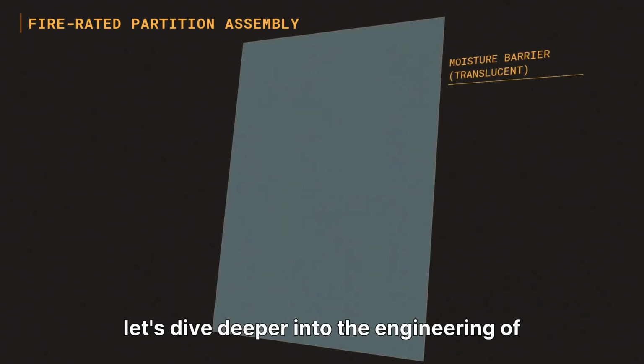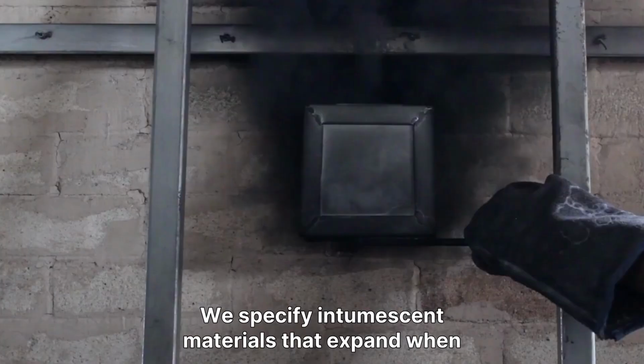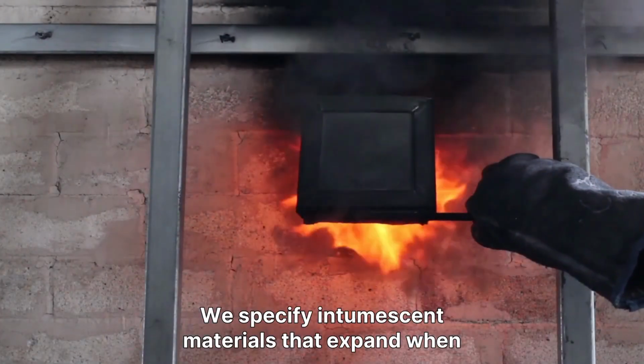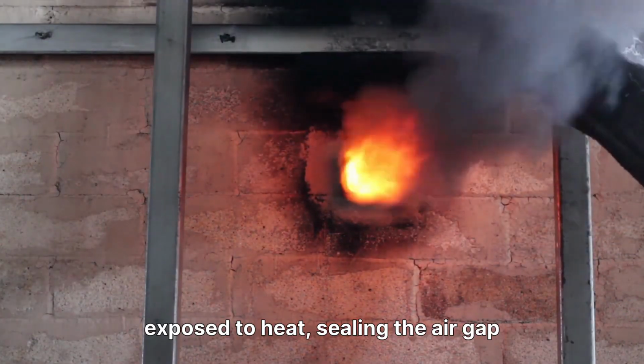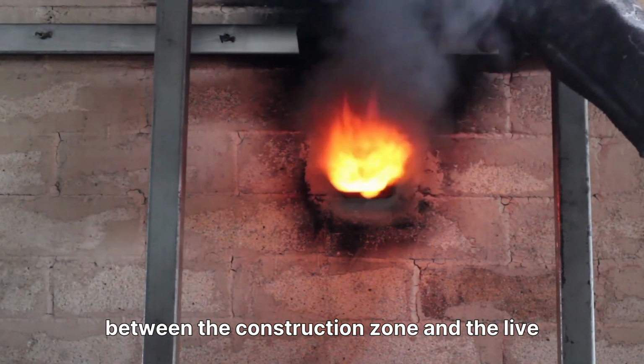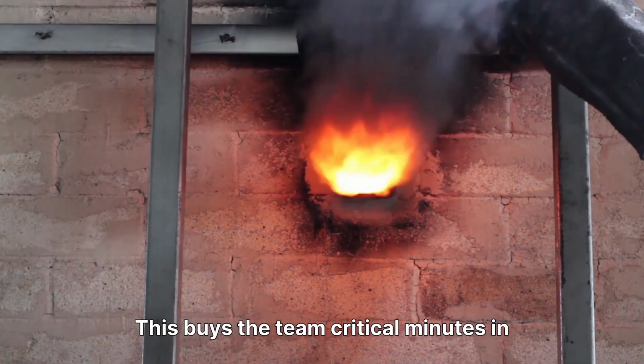To ensure we hit our 10-minute target, let's dive deeper into the engineering of our temporary boundaries. This partition isn't just about dust, it's our primary fire defense during construction. We specify intumescent materials that expand when exposed to heat, sealing the air gap between the construction zone and the live hall. This buys the team critical minutes in an emergency.